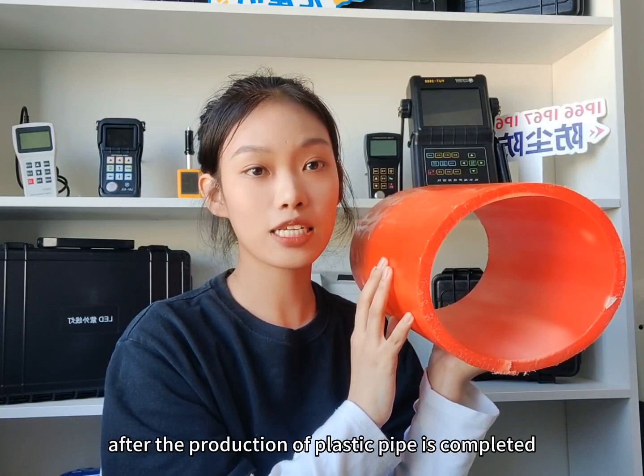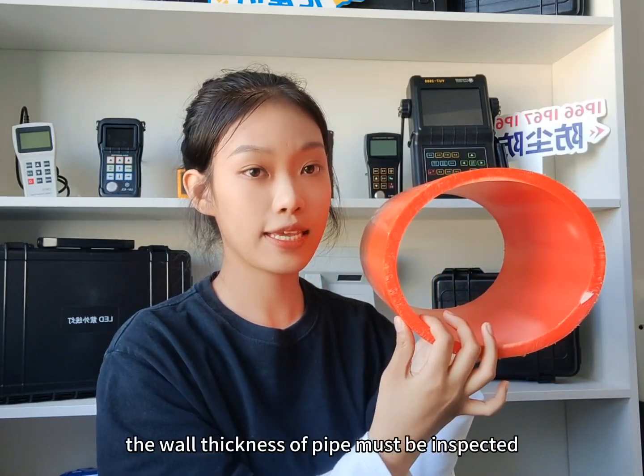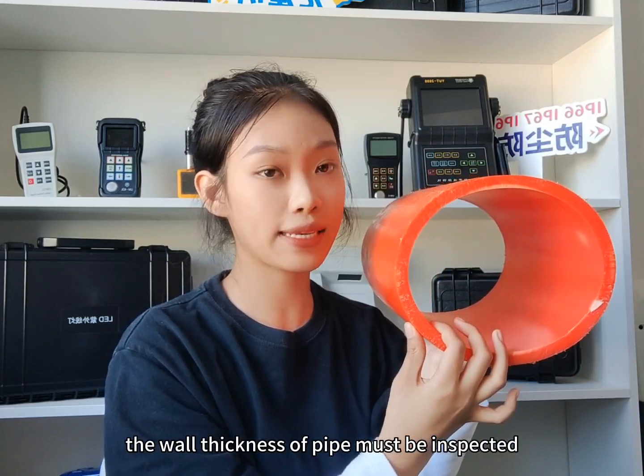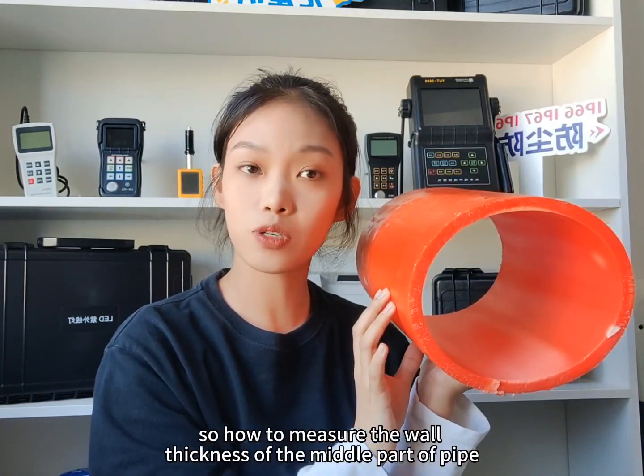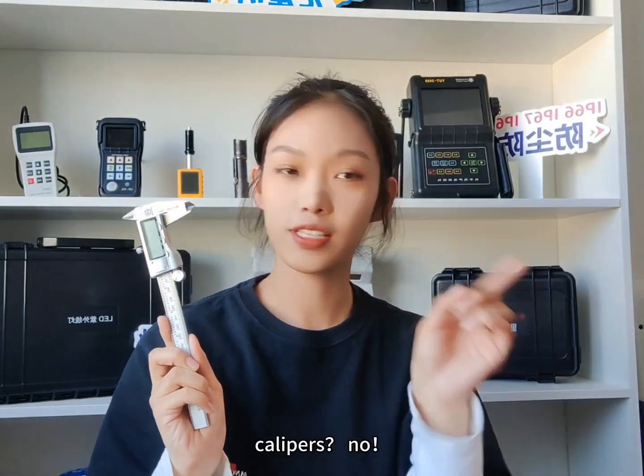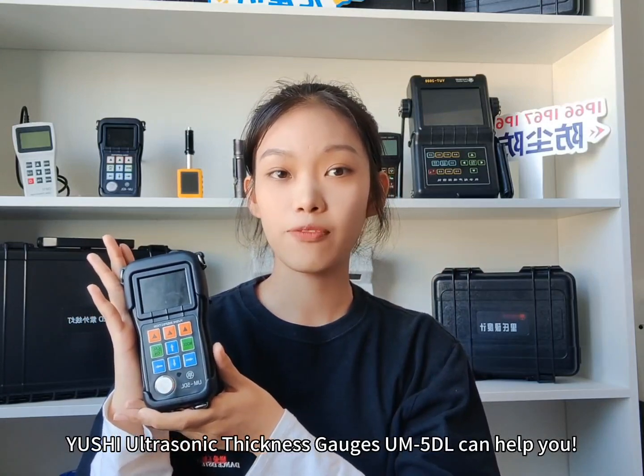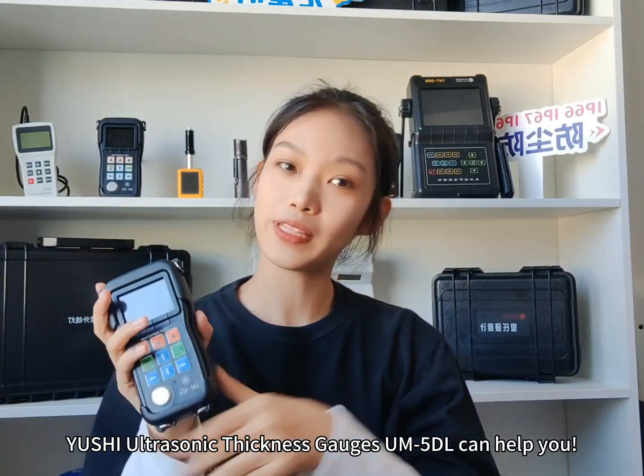We know after the production of plastic pipe is completed, the wall thickness of the pipe must be inspected. So how do you measure the wall thickness of the middle part of the pipe? Calipers? No. Yu Shi ultrasonic thickness gauge UM-5DL can help you. Let's go.